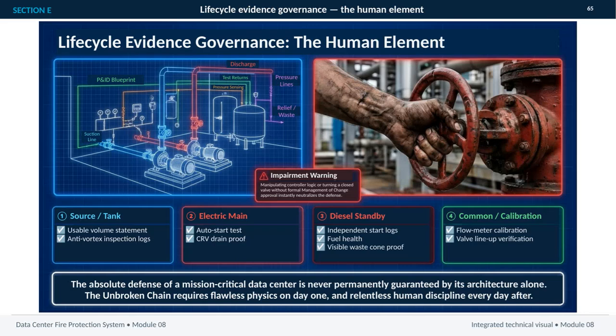No temporary bypass or abnormal valve position should survive a shift handover without formal documentation, an affected zone map, and owner approval. This slide shifts the focus from system architecture to the people who keep that architecture trustworthy throughout its life cycle. The P&ID provides the map: source and tank, suction and discharge paths, test returns, pressure sensing, relief or waste routes, and the pressure lines that support impairment warnings. But a map is only useful when the evidence behind it is current and verified.